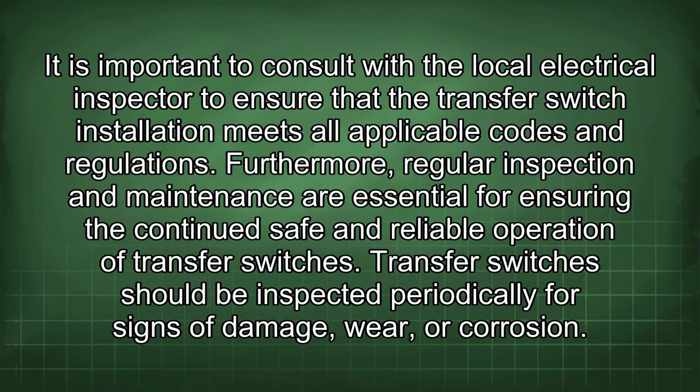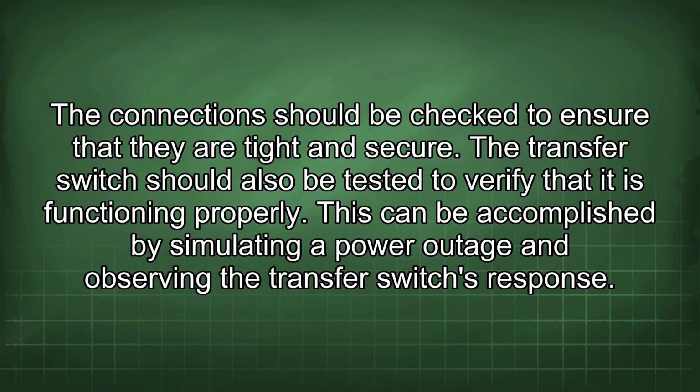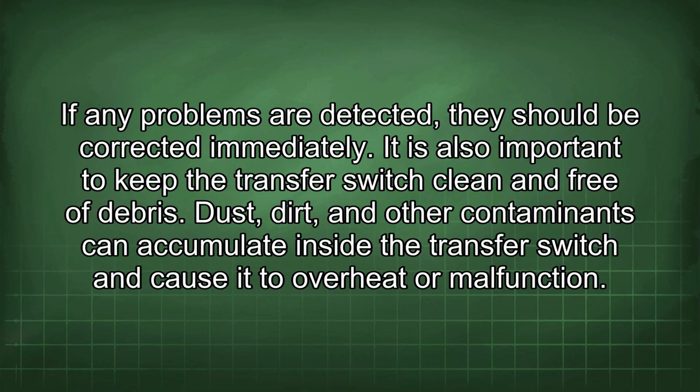codes and regulations. Furthermore, regular inspection and maintenance are essential for ensuring the continued safe and reliable operation of transfer switches. Transfer switches should be inspected periodically for signs of damage, wear, or corrosion. The connections should be checked to ensure that they're tight and secure. The transfer switch should also be tested to verify that it is functioning properly. This can be accomplished by simulating a power outage and observing the transfer switch's response. If any problems are detected, they should be corrected immediately.